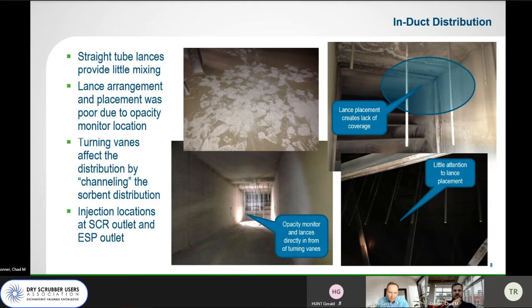So the first time I went there, we were able to do some ductwork walks, and I was able to do a thorough evaluation of the entire system. Again, throughout the industry, I think it's starting to become widely known that straight tube lances don't give you any mixing. Basically, the hydrated lime streams directly downstream from them. In the top right picture, you can see the orientation of the lances in this kind of smiley face arrangement leaves a large empty or untreated hole. Couple that with the lances being located directly upstream of turning vanes, which are going to negate any kind of mixing that you had.